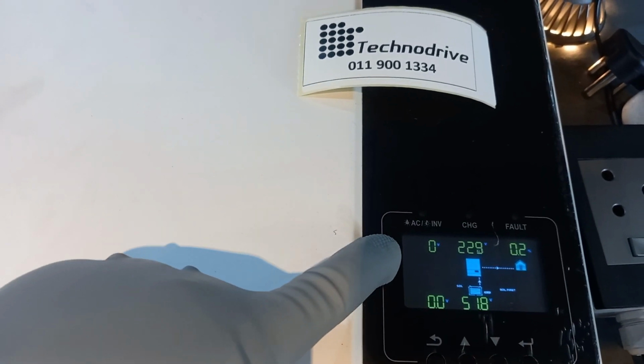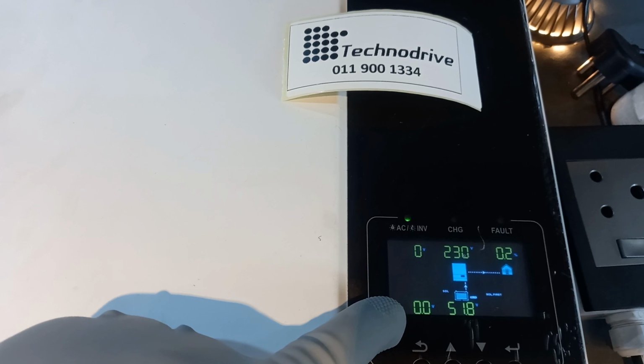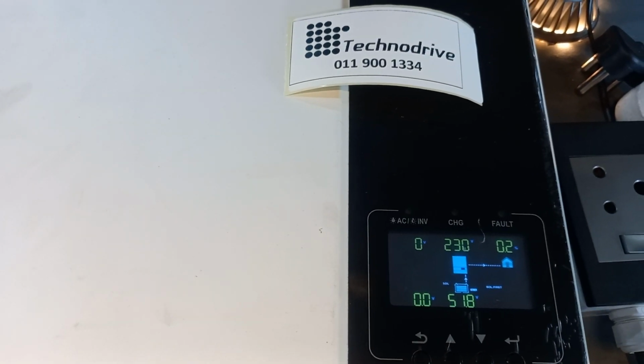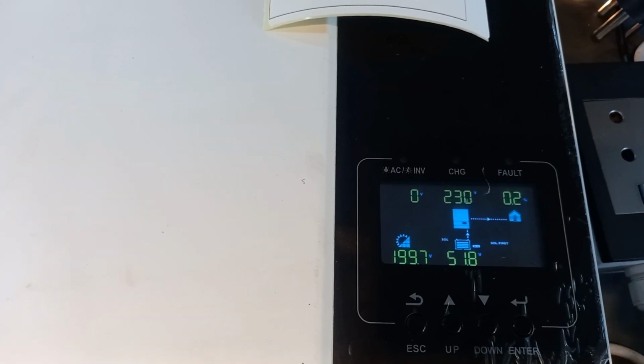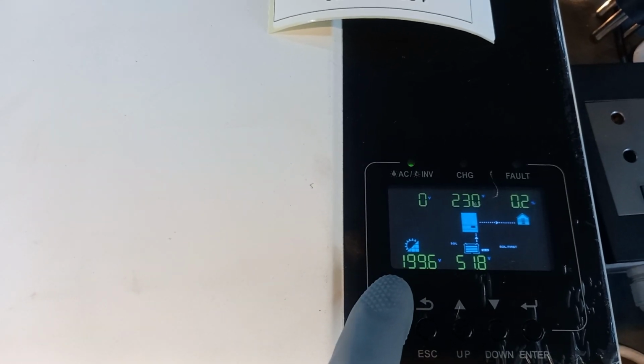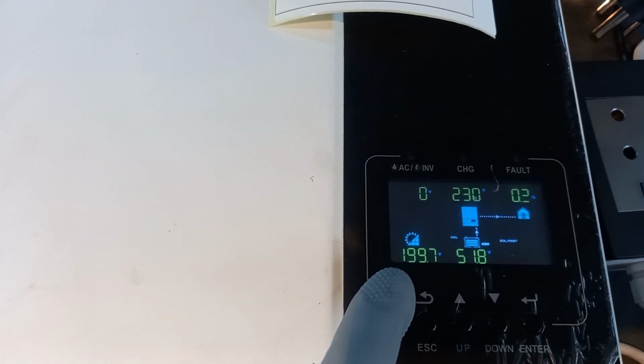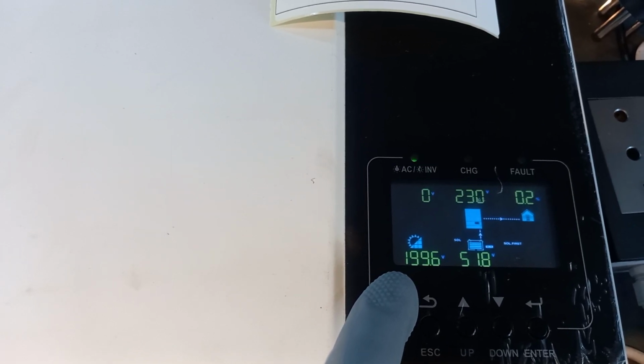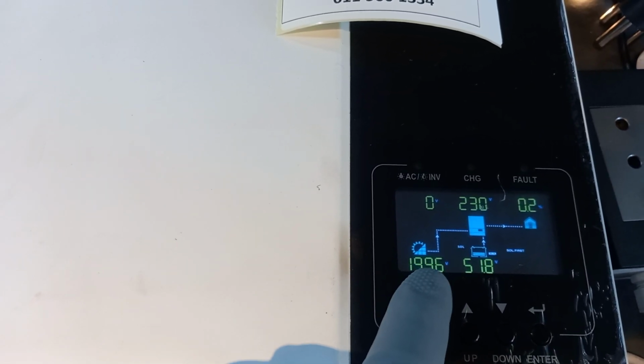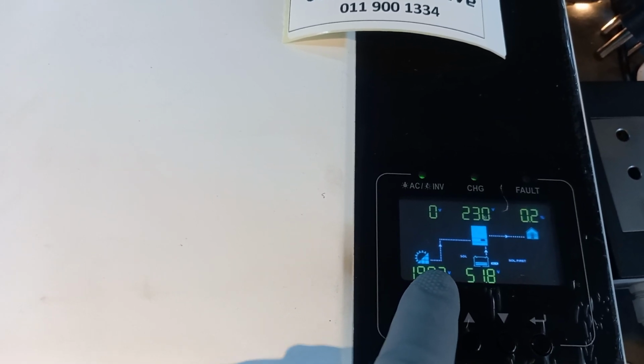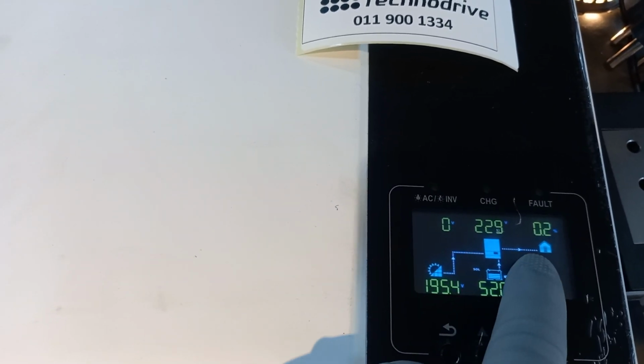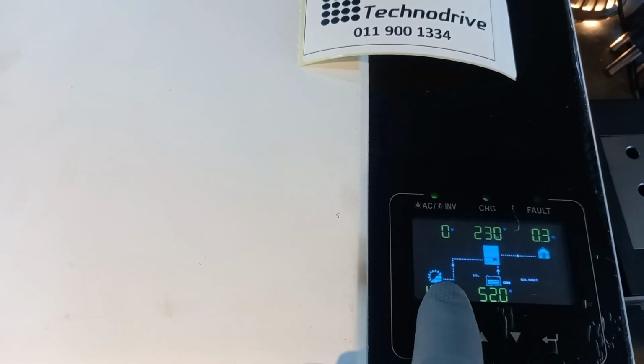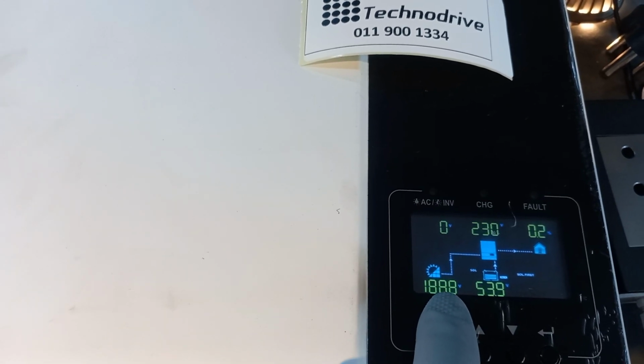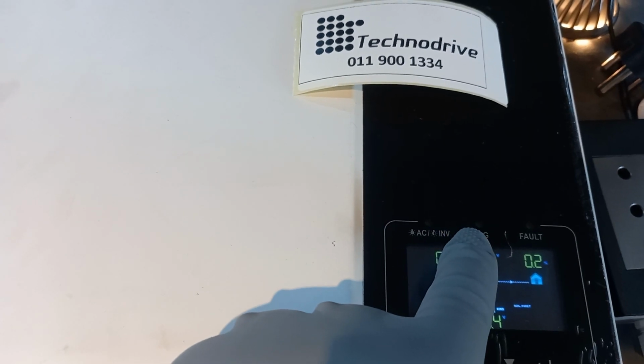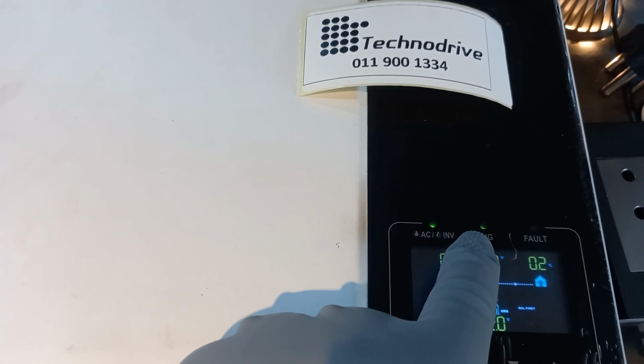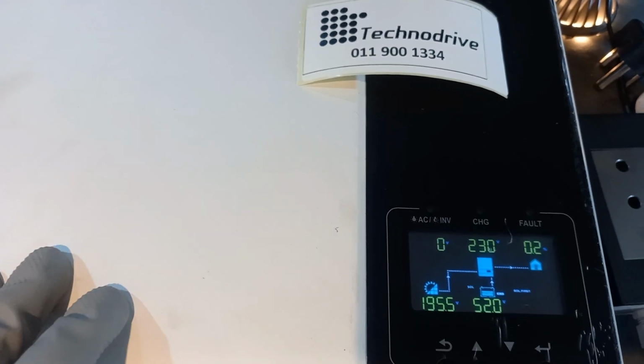Okay, you can see the voltage from the ESCOM is 0 volts and the PV is 0 volts. Let's switch on the PV. You can see now the PV is coming on. We have got 199 volts, which is almost 200 volts of the PV voltage. You will see when the inverter, okay, there it goes. The inverter is now taking power from the PV to the appliances. So the PV side is working. You can see it's also charging. So now we are using power from the PV.